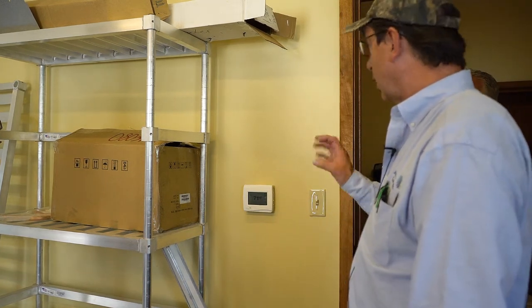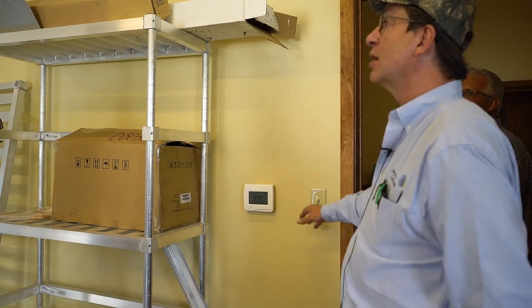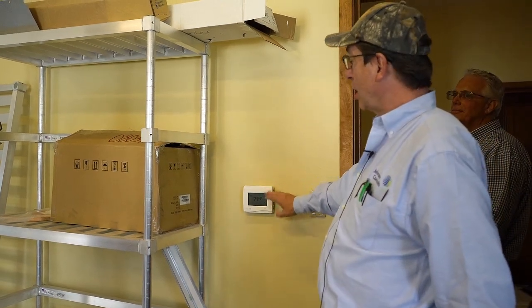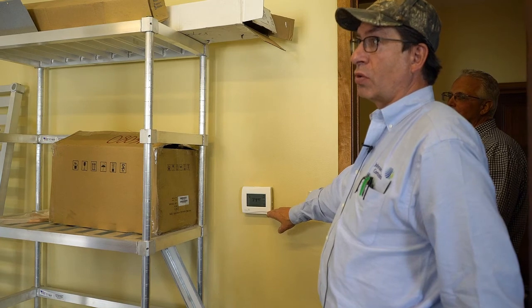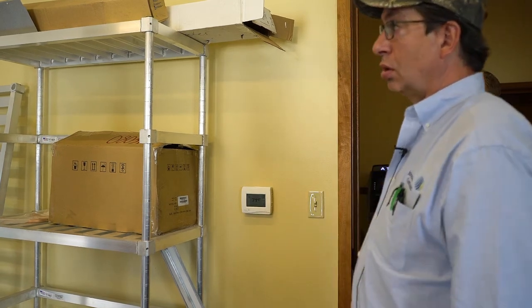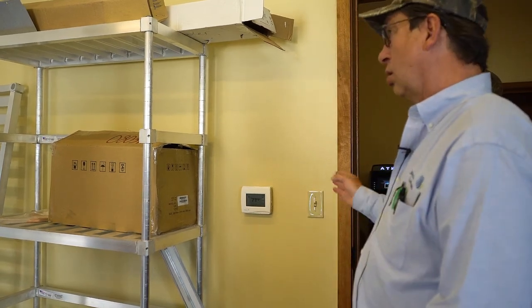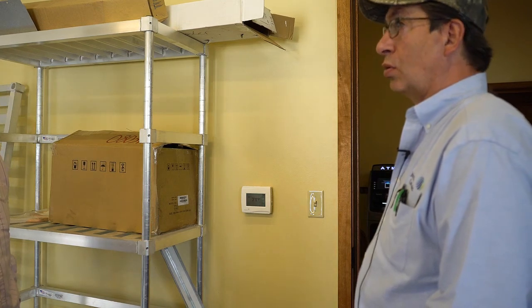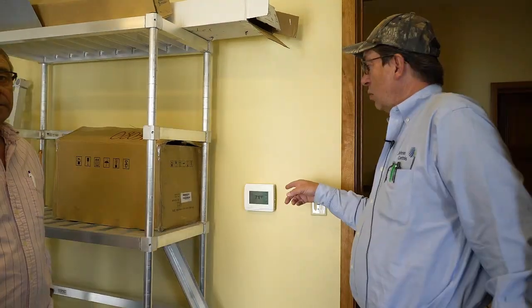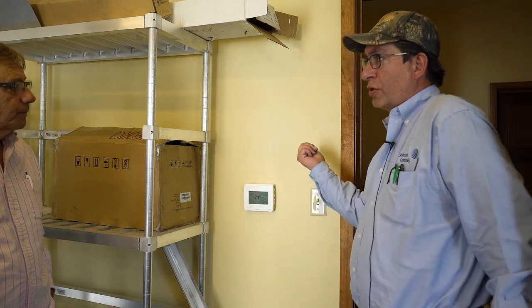But the other thing that you would have to remember to do is, since it is on our trunk, it has to be addressed the same as the one you took off here, just like a smoke alarm, or it will drop the trunk out for the whole building. So the other question that was brought up was on the other thermostats.